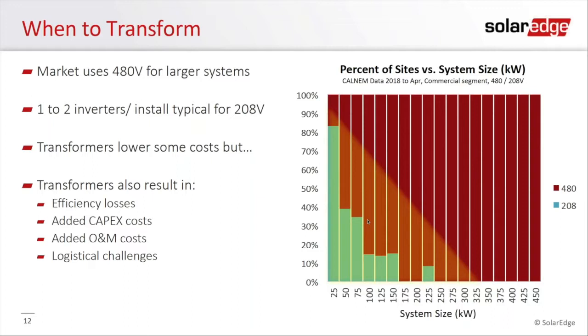And so you're looking at the blue is your 208 inverter and the red is your 480 volt inverter. And you can see that it drops off very quickly, just like our survey responses did, where right around 100 kilowatts and below, we see some pretty good markets there for 208. At 100 kilowatts and above, really minor markets for 208. Most people are using the transformers in those cases. And what we've heard in talking to installers kind of corroborates this. You'll look at about 1 to 2 inverters to do a 208, and then you're usually going to a 480 volt inverter and using a transformer.